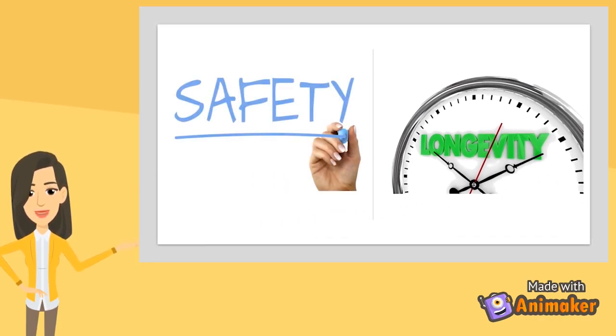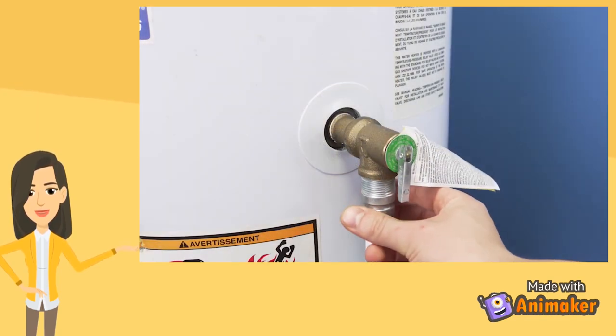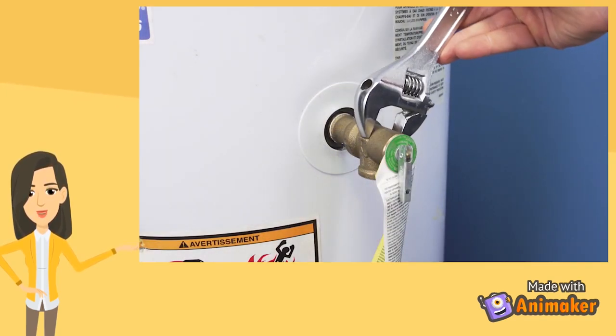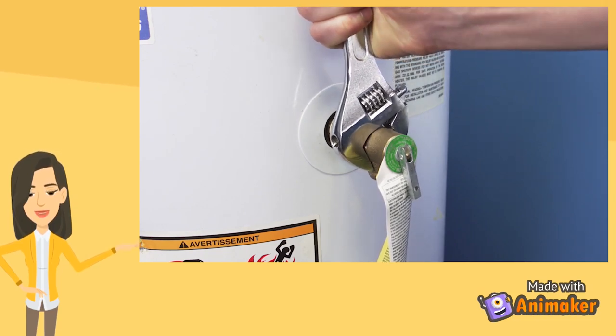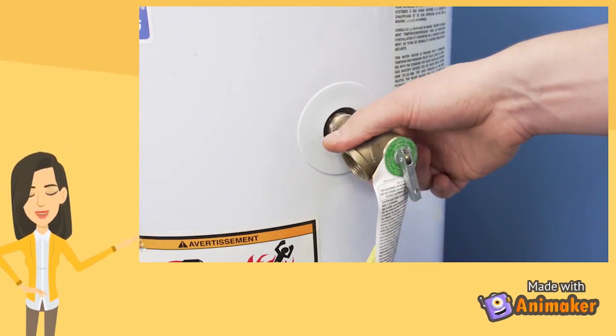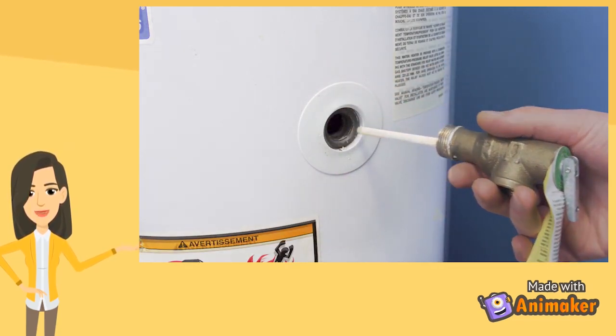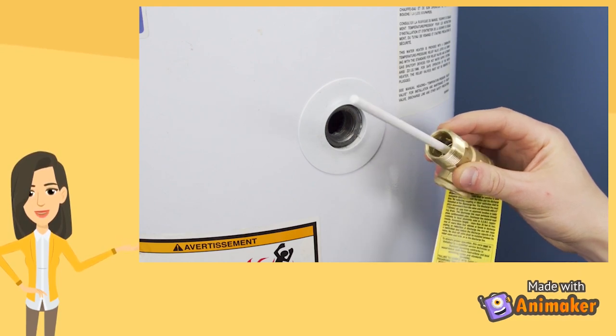TP valves should be inspected and tested on every service call. Many changes may take place in the plumbing system after the original installation. It is important to note that during South African summers or when the house has been left vacant for a period of time, it is quite common for TP valves to accumulate a lot of wear and tear, and thus they will most likely malfunction.